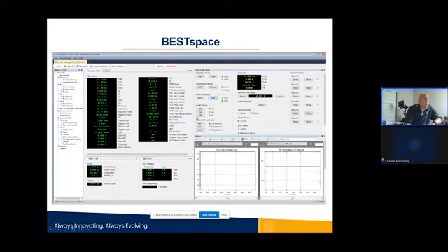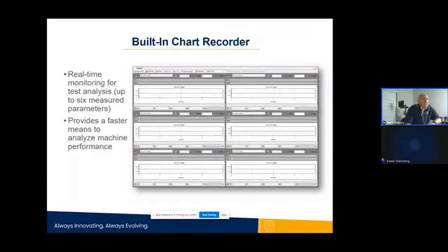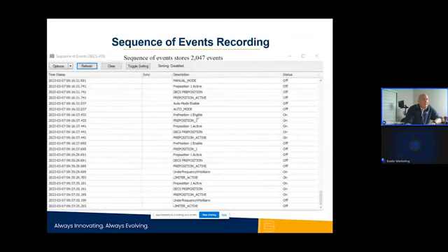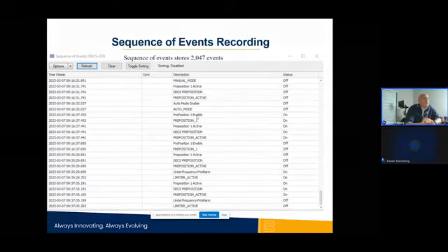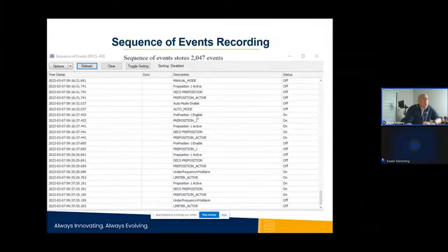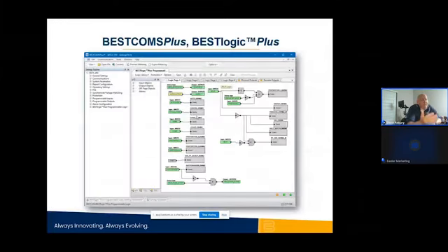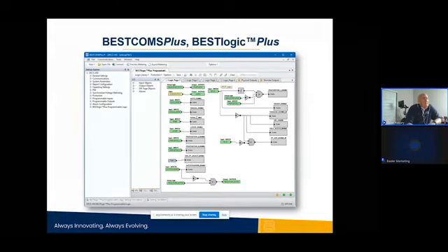Our real-time chart recorders give us the ability to look at the system while we're doing response tests. The sequence of events is a great troubleshooting tool. It gives you everything that motor was doing for the last 2,000 events. And then there's the programmable logic. A lot of this will be gone over probably in a month, when we do BESTCOMS Plus training for the excitation control devices.